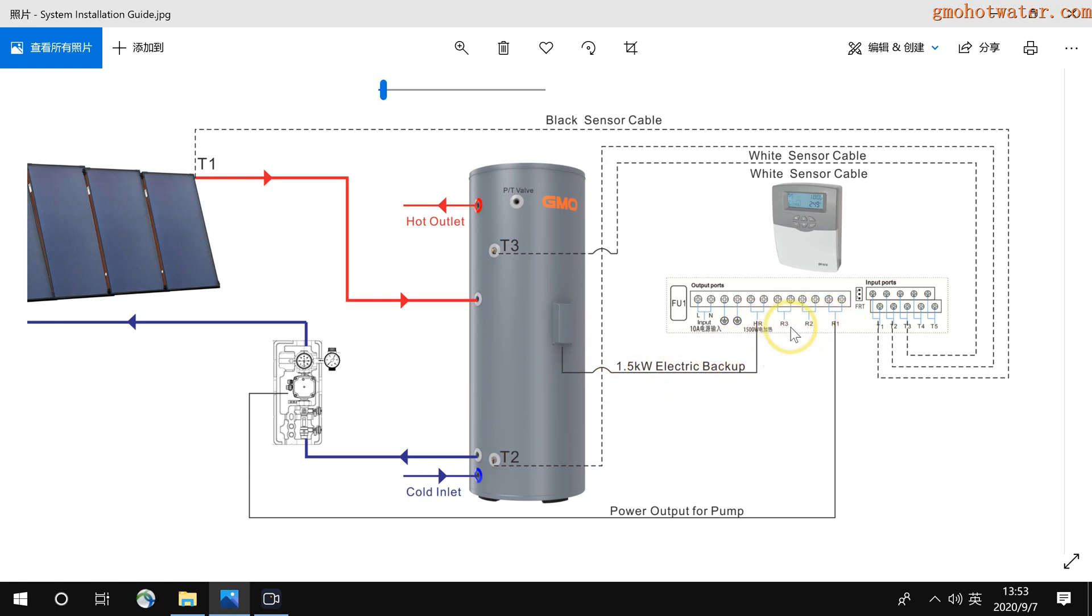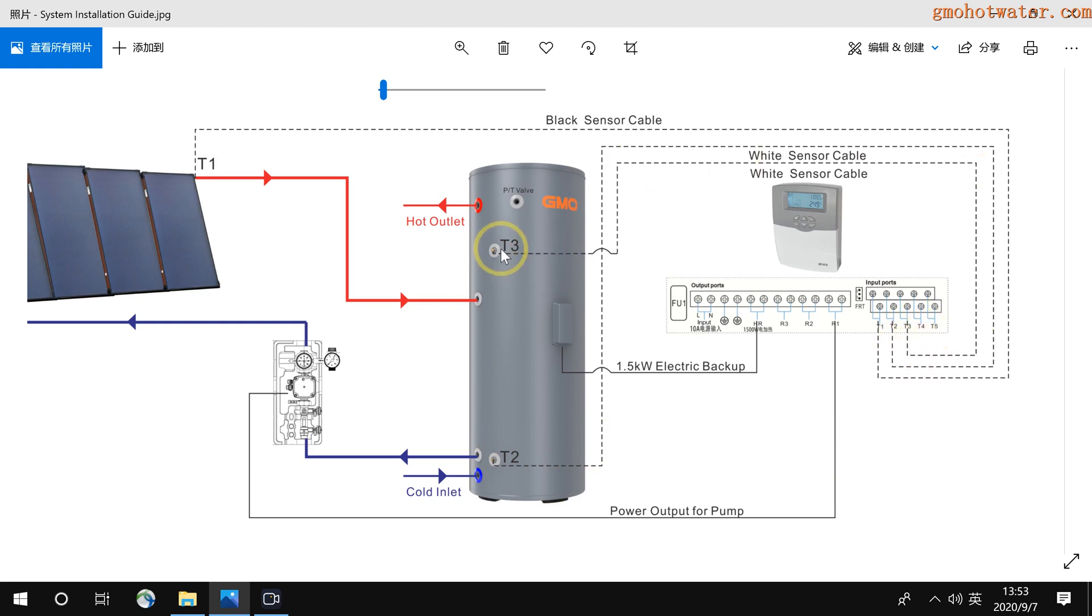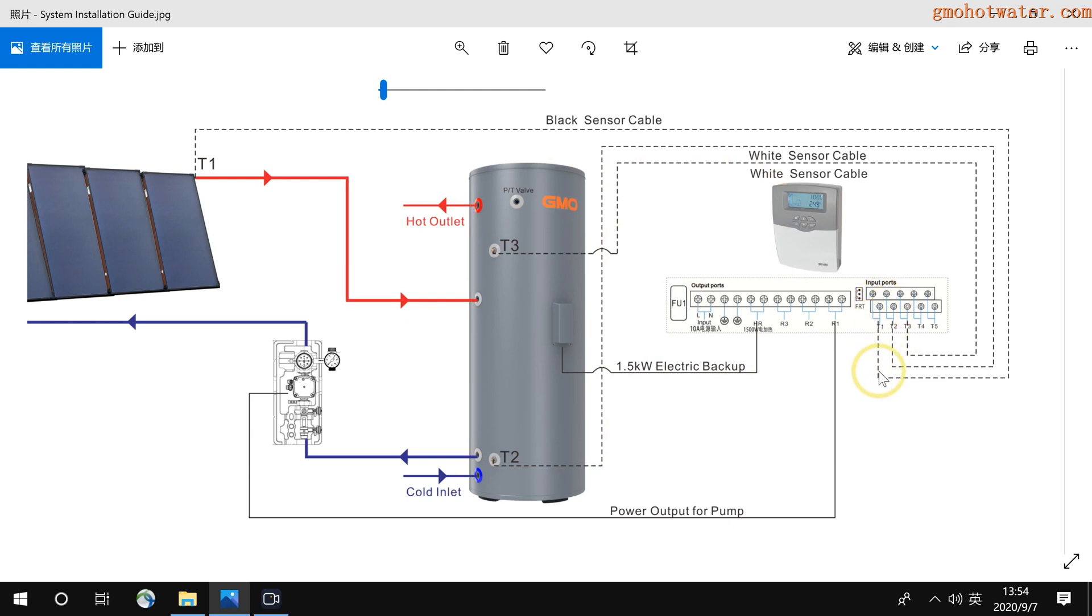R1, R2, R3 are used to connect to the pump. For this system, we just need to use R1 to connect to the pump station. And T1, T2, T3 - T1 is for the flat panel sensor, T2 is used to detect the bottom of the tank, and T3 detects the temperature at the top of the tank. You just connect the sensor according to my pictures. Don't mix it. So please fix the sensor, connect the sensor to the terminal according to my pictures, one by one.